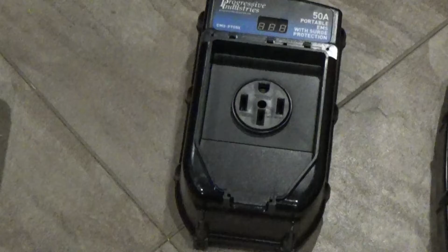What both of these units do when they detect low voltage is cut off the power to the RV. It just shuts down power at the point of 104 volts. If the voltage goes below 104, it shuts down power, and if it comes back up above 104, it automatically turns the power back on.